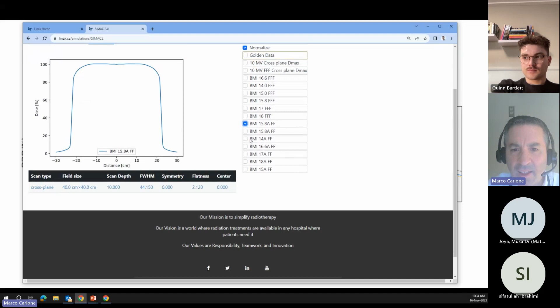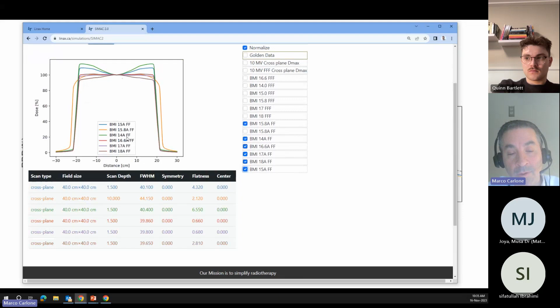So here, again, we see some of the beams. The one with the 18 amp bending magnetic setting is the highest energy beam. This one has a profile with the highest intensity at the center and lowest at the sides. And then the green beam over here is with the 14 amp flattening filter setting, which is the lowest energy, and its flatness is very different because it's lowest at the center and highest at the sides.